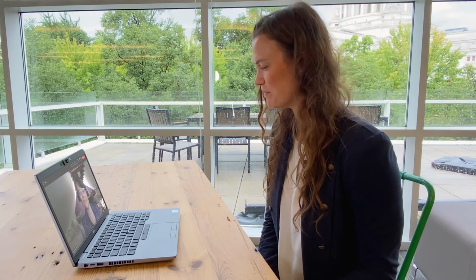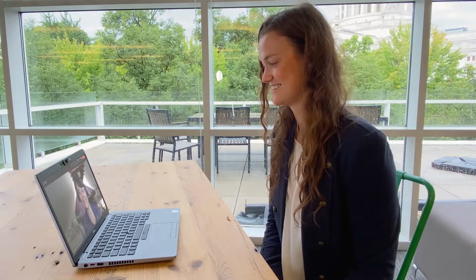Now, can you tell me more about controls? What am I supposed to do there? I'm so glad you asked about that. If you have a balanced ventilation system, you really do need to know how to operate it. The best setup, as I said, is continuous ventilation. Since your ventilation air is riding along with the heating and cooling air, that means your heat pump has to circulate the air also. There's a ventilation setting on most modern heat pumps and air handlers that moves just enough air to distribute the ventilation. When you need more ventilation air, use the ventilator control to put the ventilator on high speed. Most controls will return the ventilator to normal speed after some given amount of time. And importantly, don't ever turn off the ventilator or disable the continuous circulation of the heat pump. And that will make sure that you're just always getting ventilation air.